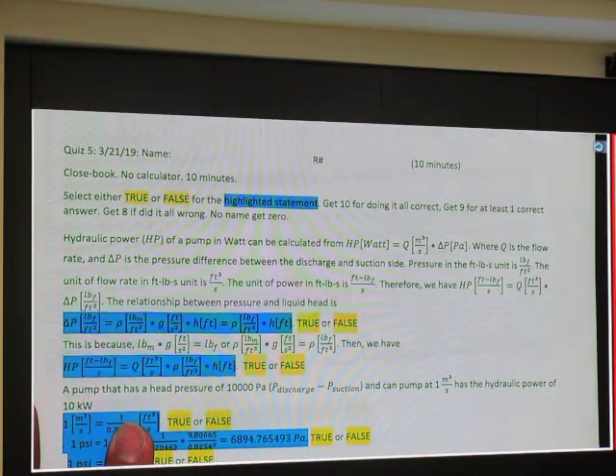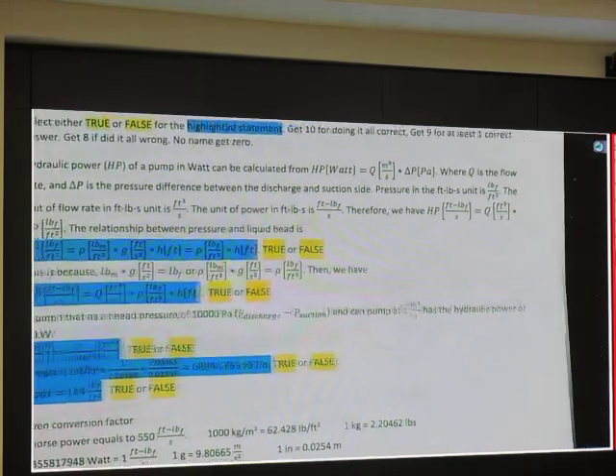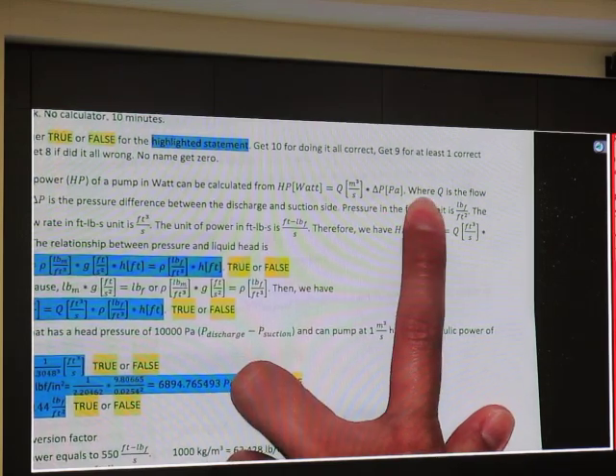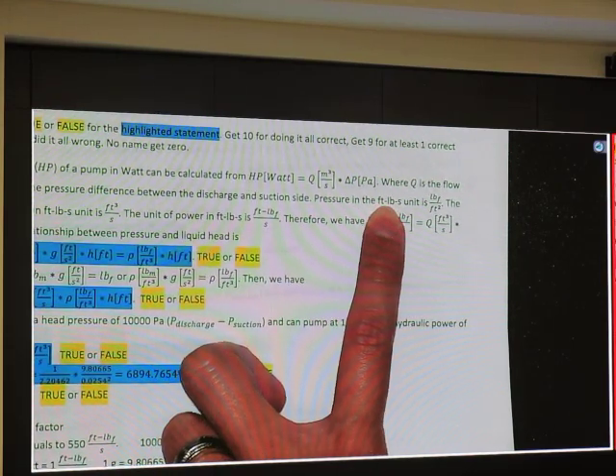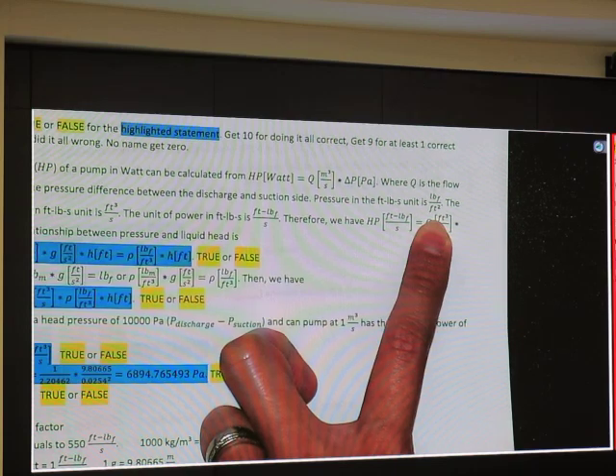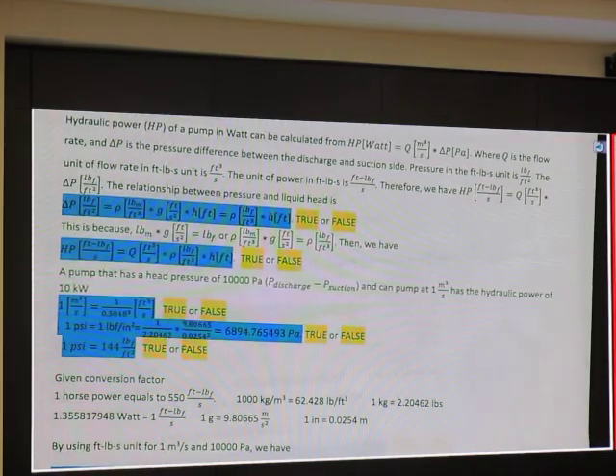Select flow of pumps. Hydraulic power of a pump in watts can be calculated from flow rate multiplied by delta P. You got that, right? Q is the flow rate. Delta P is the pressure difference between discharge and suction. Pressure in pound force per square foot.